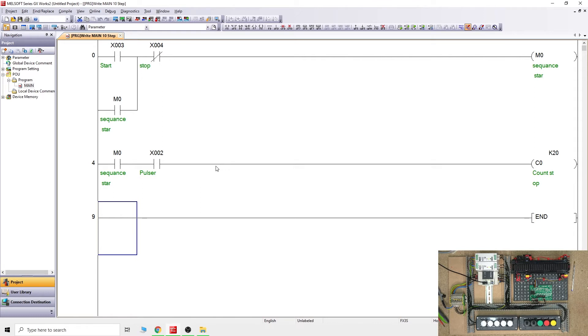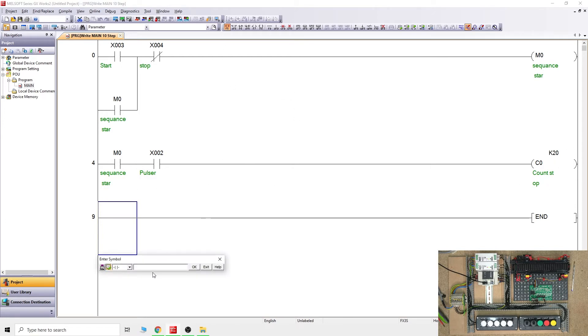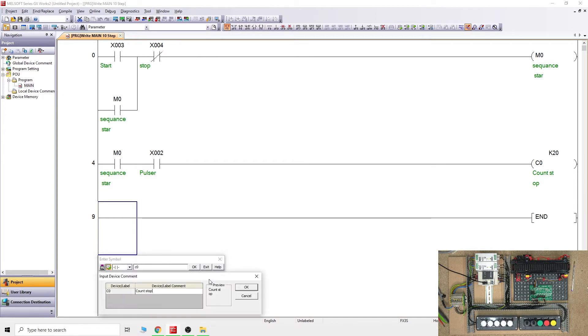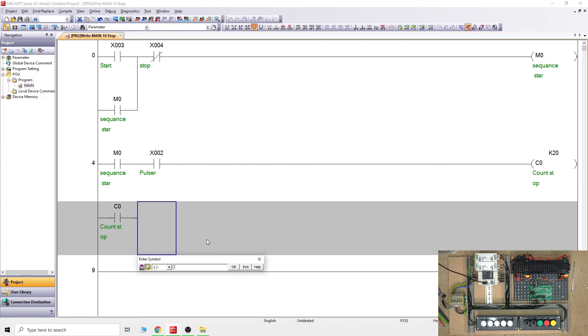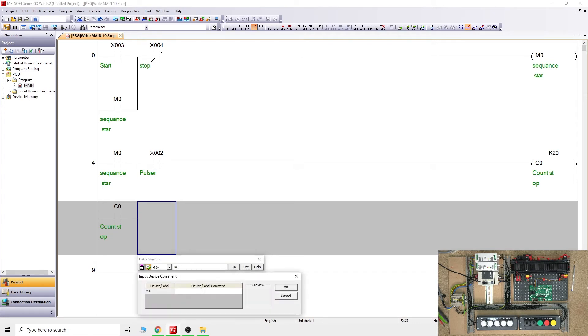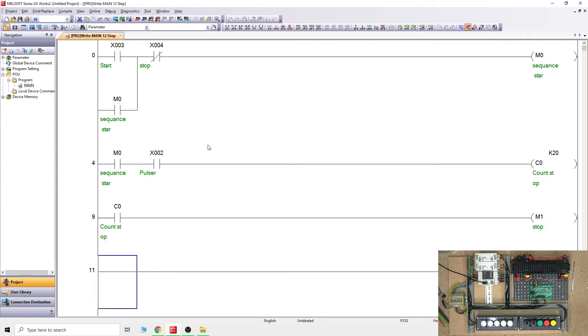Make sure there's always a space in there. Then we're going to call it count stop. A counter by itself needs to be reset - it does require resetting. Once M0 comes on, X2 will pulse till 20. What we're going to do with that, C0 becomes as a contact now, so we'll call it C0. Once the contact is reached, we'll activate another coil, M1, which will be our form of stop.